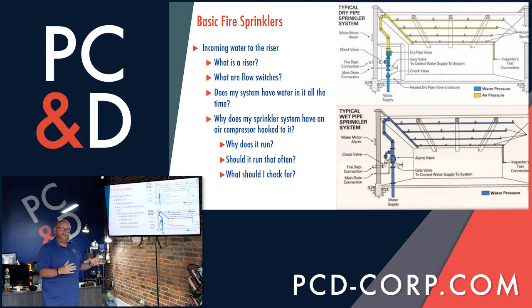Some systems will have a booster pump. So when the unit trips, the booster pump will kick in. And again, I'm gonna pull a number out of the air. If your municipal water coming in only has 100 PSI, but you maybe need 112 PSI from an engineering perspective to reach that furthest head in 30 seconds, that booster pump will be sized and engineered to boost that pressure up to that minimum of 112 or higher so that that furthest head has water at it in 30 seconds or less. So that is kind of a generic overview of wet systems and dry systems.